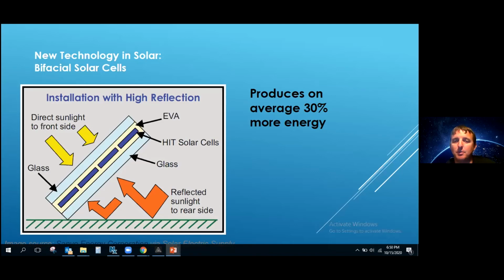On average, these bifacial panels can produce 30% more than a standard single-sided panel. It makes sense for some cases, probably not rooftop mounted since there's no reflected light on the backside, but for large solar farms where the backside is open and tilted towards the sun, a bifacial panel would produce a lot more energy in the same area. You're taking advantage of the sunlight hitting the ground behind the panels, since you don't want to fill up the entire space next to the panels, or panels would be blocked when the sun changes angles.